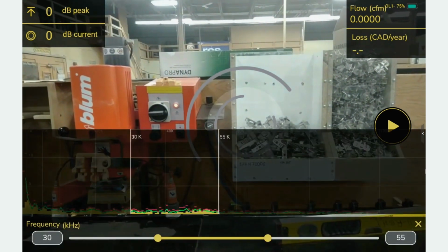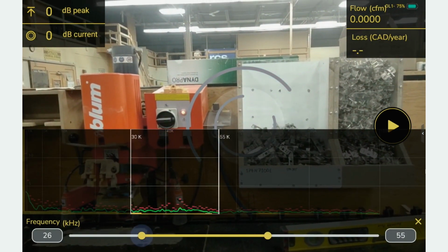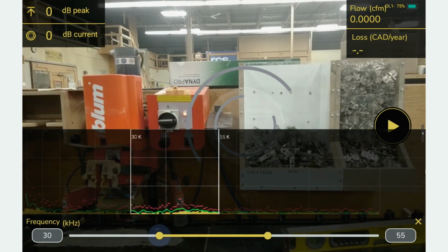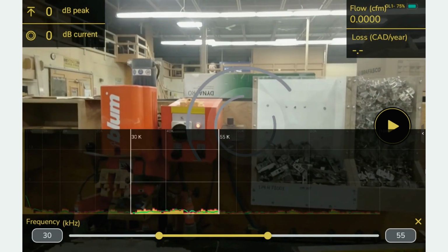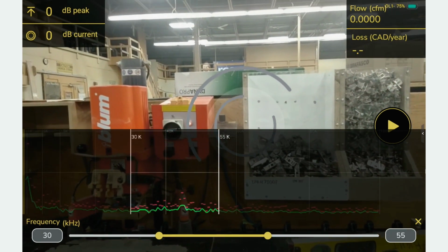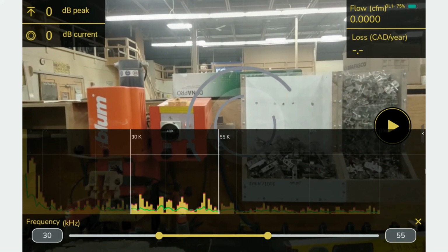Settings provide your real-time FFT to check for background interference and to set both upper and lower bounds accordingly. The FFT is a key place to visit at the start of each audit. This gives the user an indication of the background facility noise characteristics.